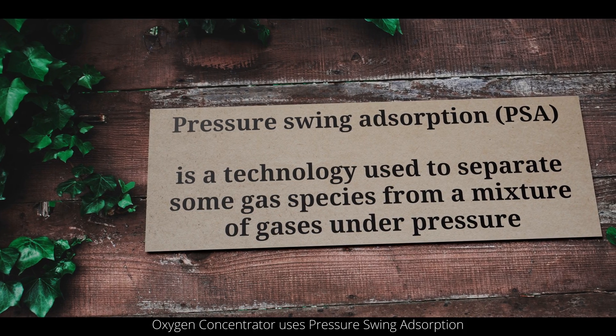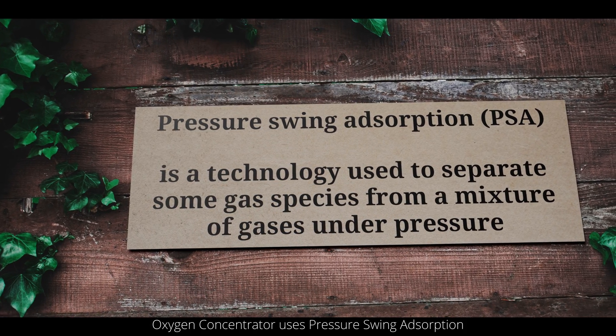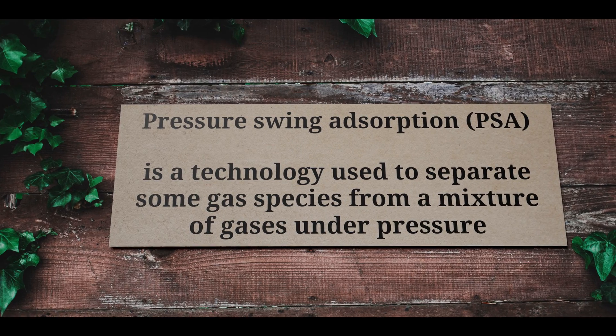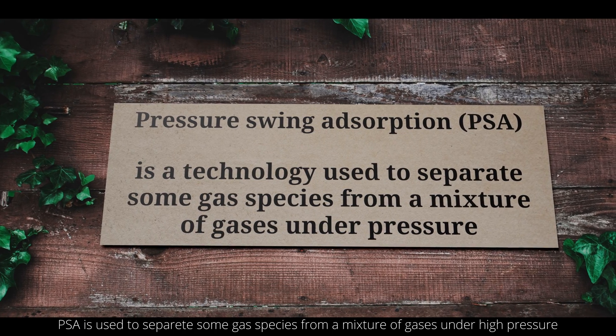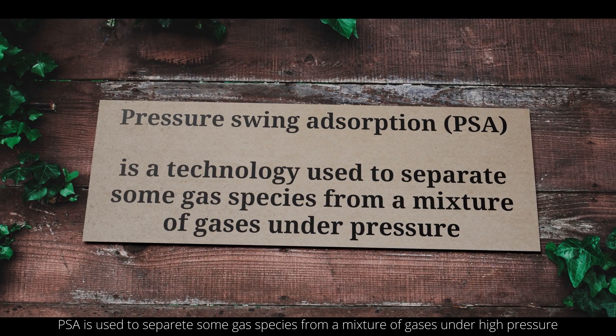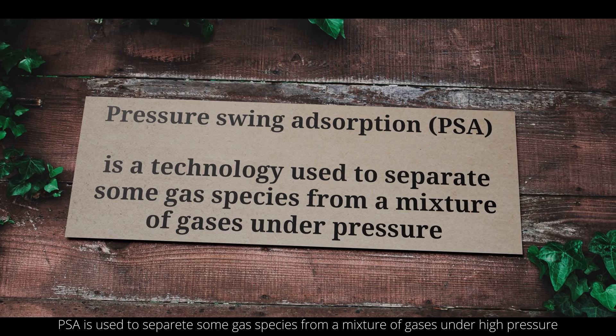An oxygen concentrator uses Pressure Swing Adsorption, or PSA, technology. PSA is used to separate some gas species from a mixture of gases under high pressure.